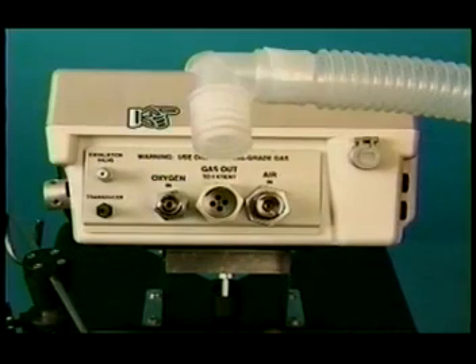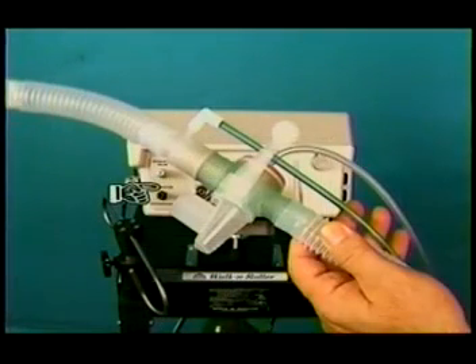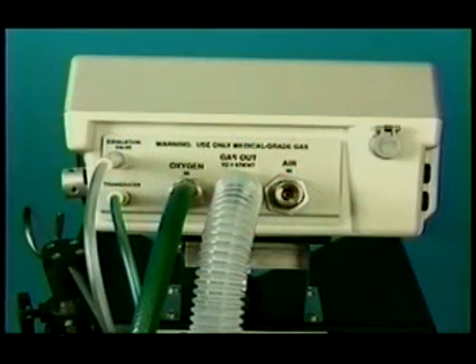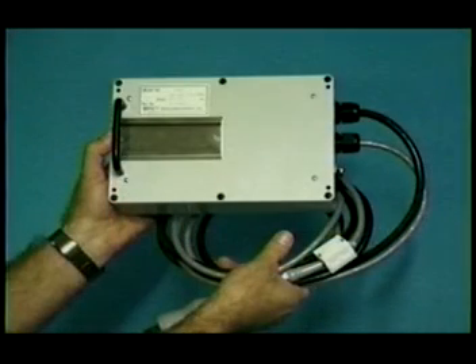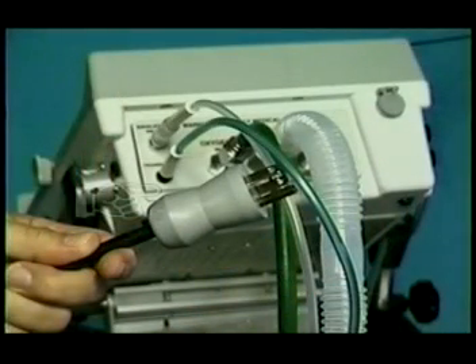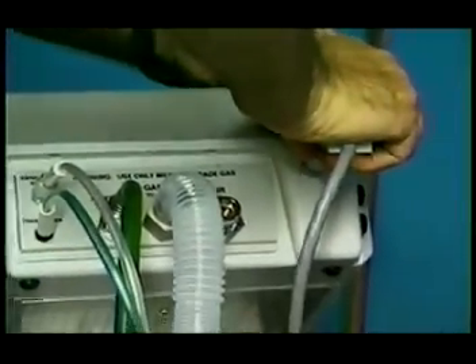The patient connector is a small elbow. It connects to the exhalation valve via a short 22mm tube at one end and the patient's endotracheal tube at the other end. We've attached the ventilator circuit tubing and the oxygen hose. Now we will connect the external power supply. The external power supply has a black AC line cord which directly connects to AC mains rated between 90 and 260 volts. Voltage and line frequency are automatically sensed in the power supply. A gray output cable connects to the ventilator's external power jack.